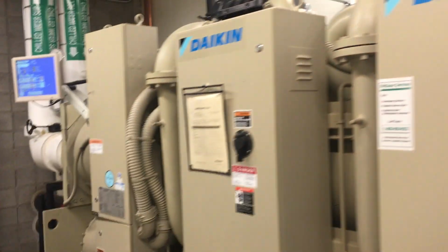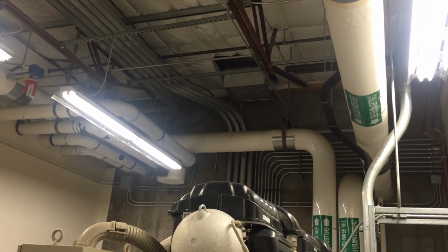I remember I did a lunch and learn on this, and my best argument for using VRF is mainly that it's a better use of space. If you take a look at, let's say, a central chiller plant, or even just a whole mechanical room with a chiller, a boiler, and all the required accessories when it comes to a chilled water system, you obviously have your chiller, you have your boiler, your air handler to move the air throughout the building, and then you have a cooling tower. You also have pumps, you also have VFDs for those pumps, and you also have the chilled water and hot water supply and return piping, which depending on the size of the system can be 8, 10, even bigger inches in diameter.